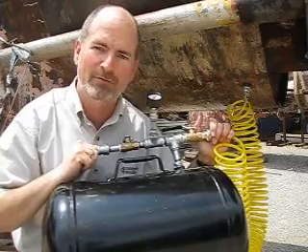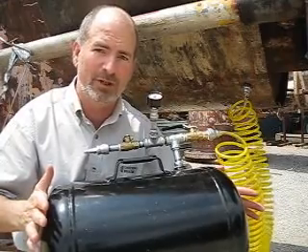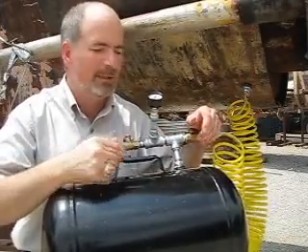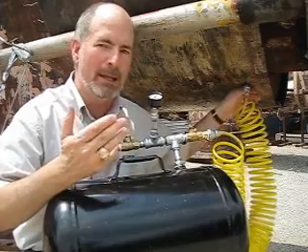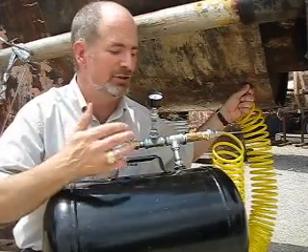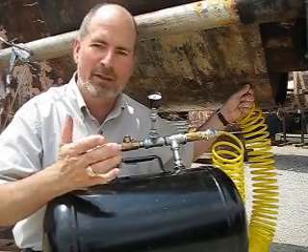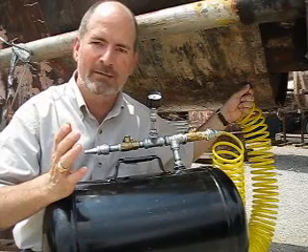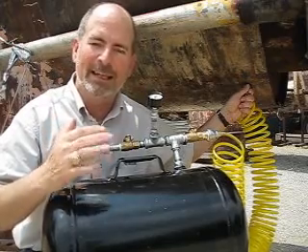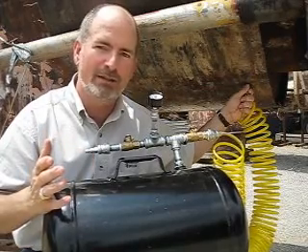We charge this thing up with 15 psi, maybe 20 psi, and then we shut it off. This is a shut-off closed system of 15 psi. Then we go in here and we tap it right in here. We open the gauge up, and you'll get an initial drop in pressure, and in about another 5 minutes you may see another slight drop in pressure, maybe a pound or two, because of what I just described, and then it'll hold steady. So you might want to start with 20 in there, but then you won't go below 15. And then you can leave that for 30 minutes, you could leave it for an hour, you could leave it overnight. And that way, that is a foolproof test that keeps you out of trouble from causing a potential overpressurization in that area, and then you can move on to the next bellows.